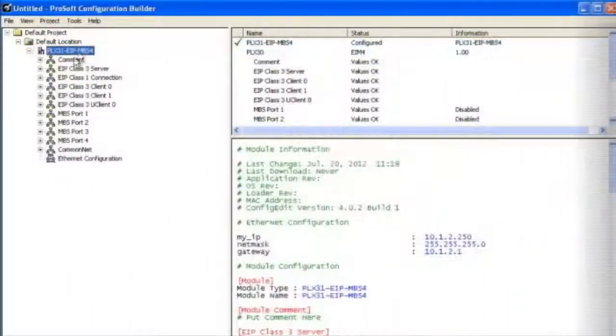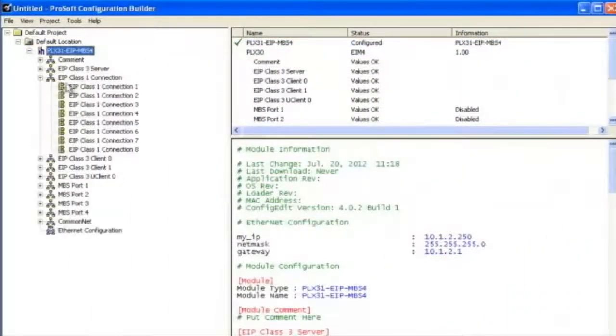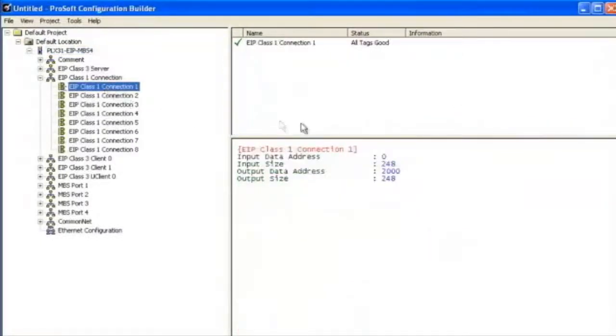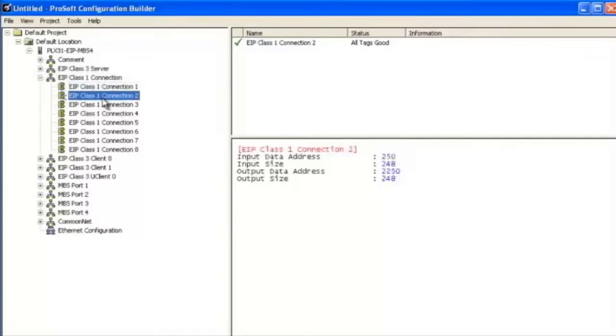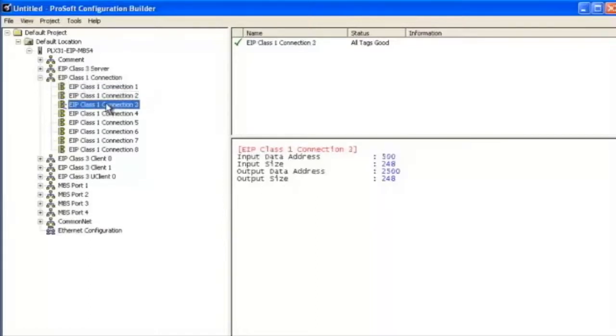Now we'll go over the EIP class 1 connections. Number of connections may vary depending upon your module. They have a 248 word input size and 248 word output size. They increment by 250 words at a time, starting at input at zero and output at 2000. I'm going to leave all these as is.